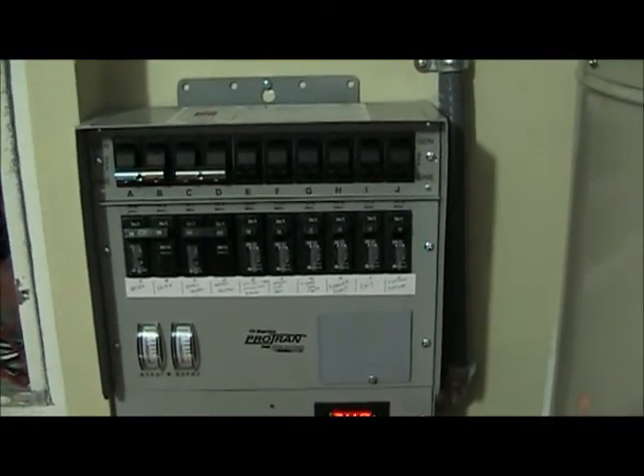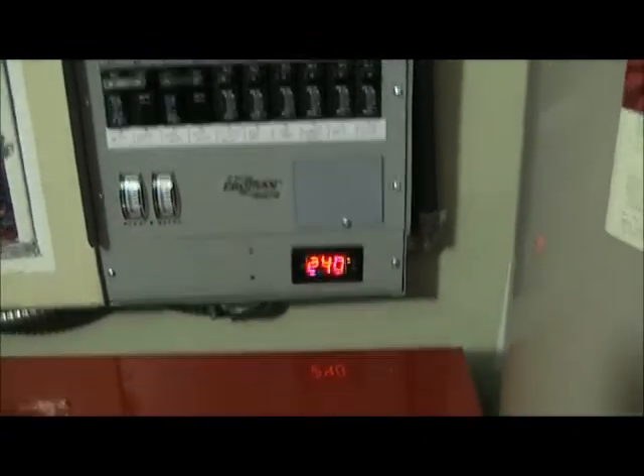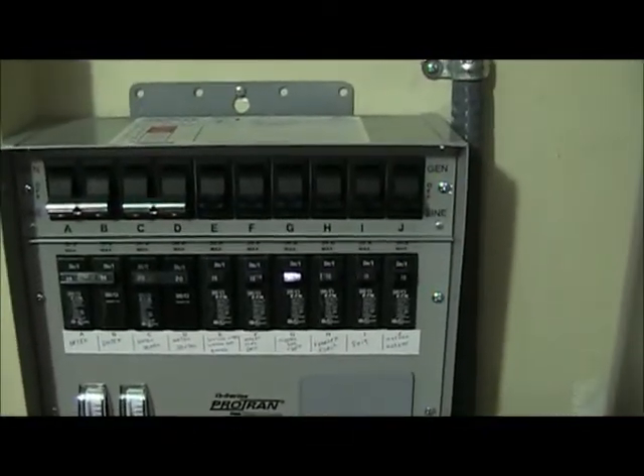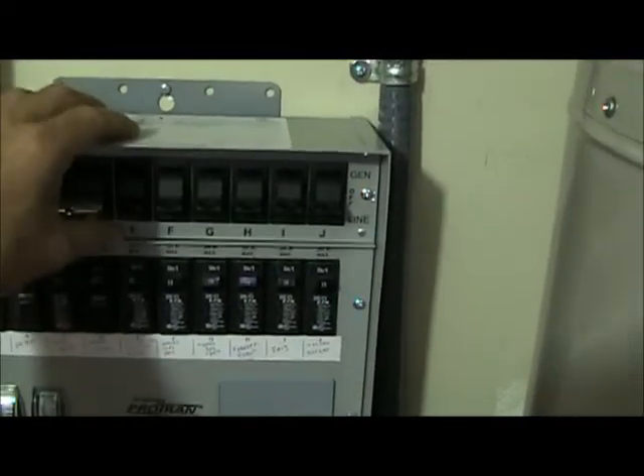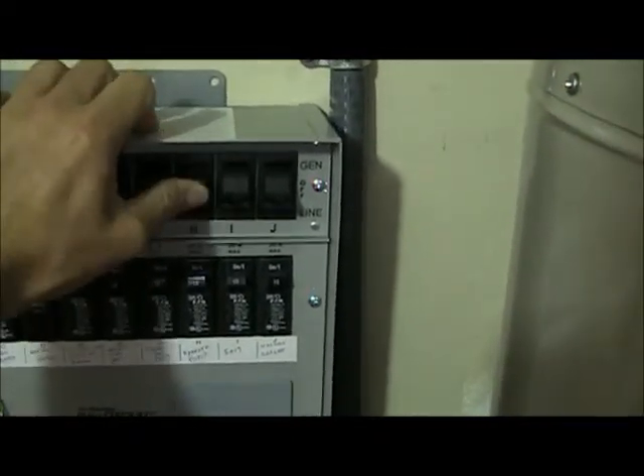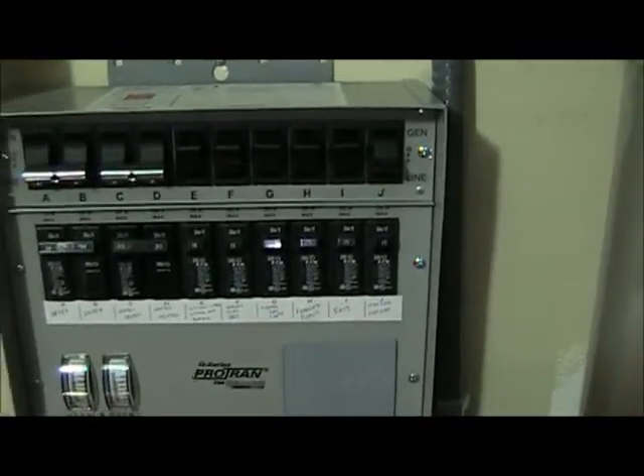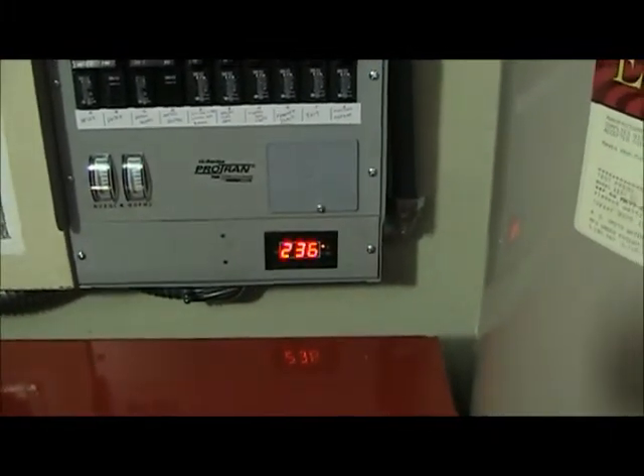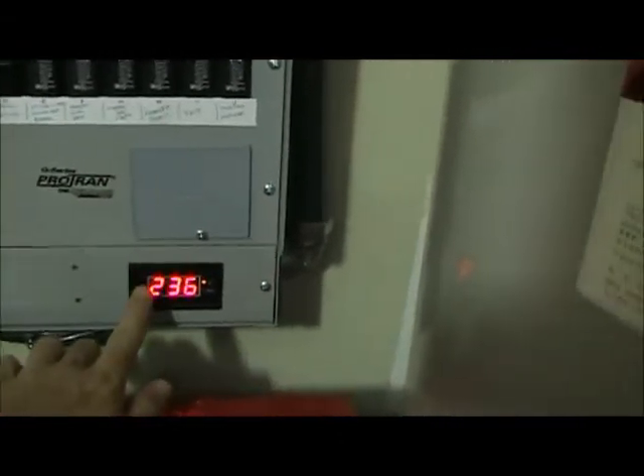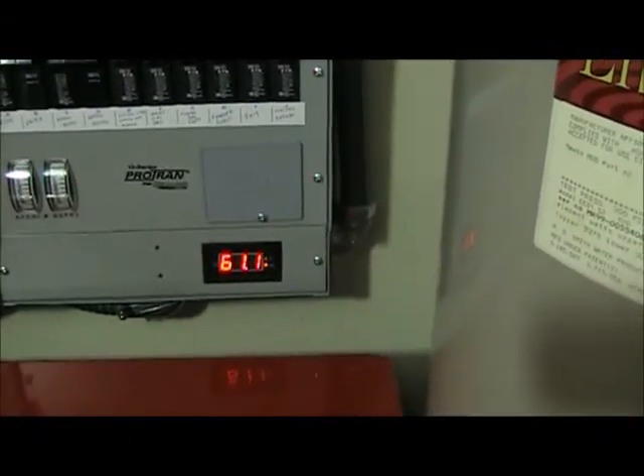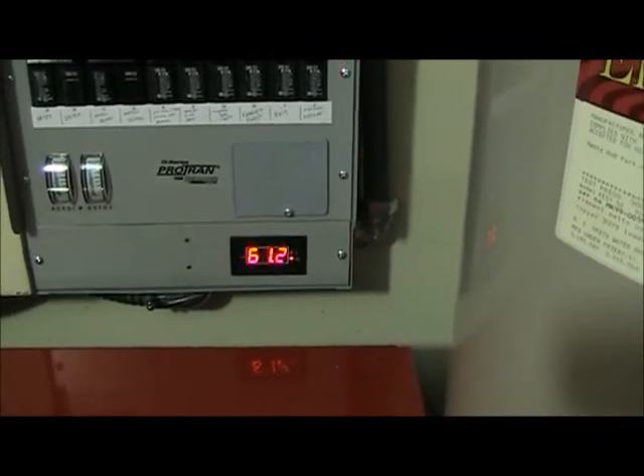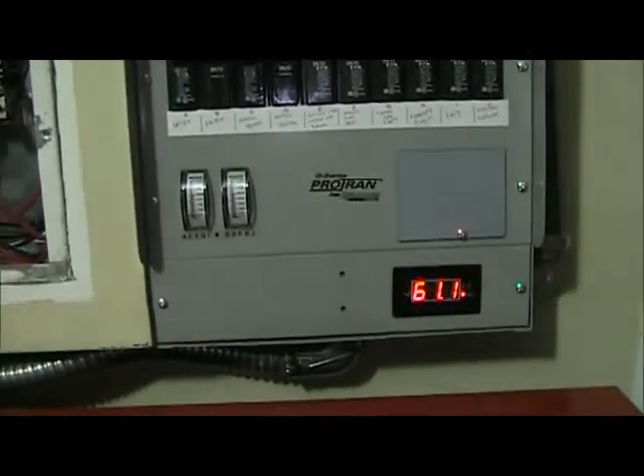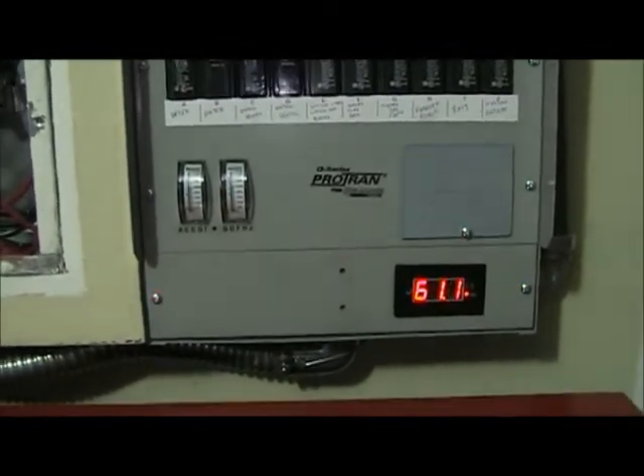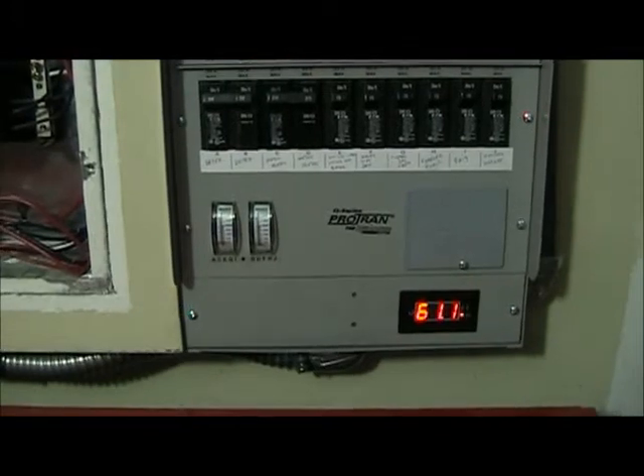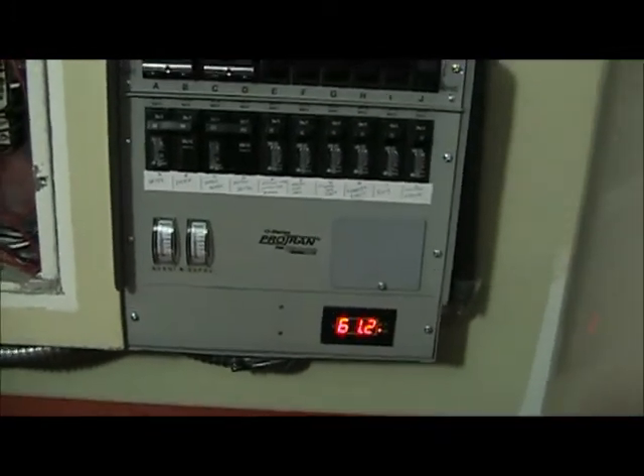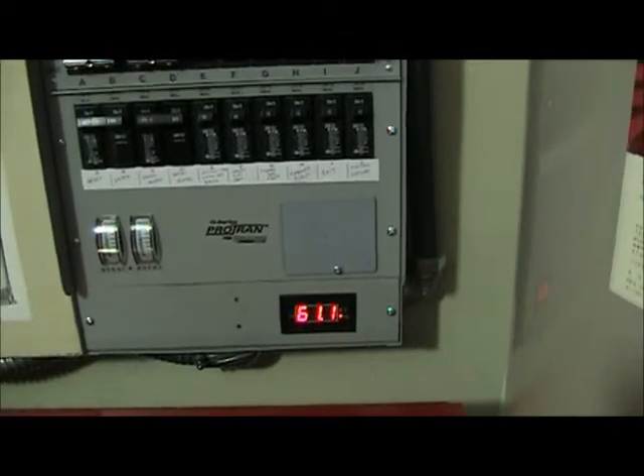So now that we have power from our genset, we can flip over here and start using some of that electricity. What I do is transfer all my 120 volt loads, and now our voltage has dipped to 236 volts, and we're right at 61 hertz for the frequency. There's two little analog meters on here, difficult to see on video, showing anywhere between 800 and 1,000 watts of electricity right now. The lights and TVs are running in the house, and the ceiling fans are going.